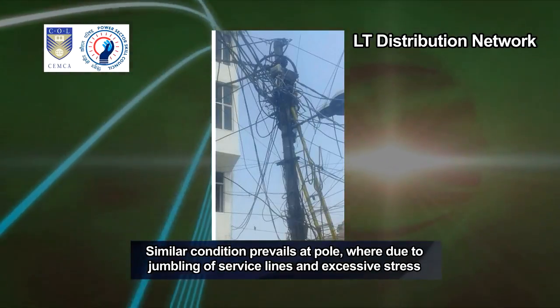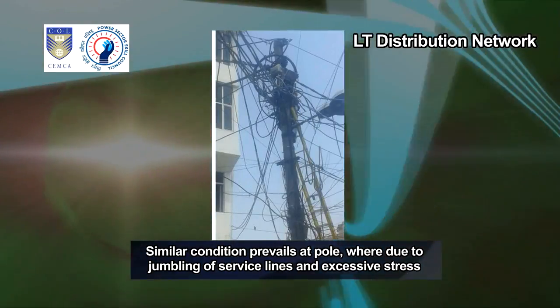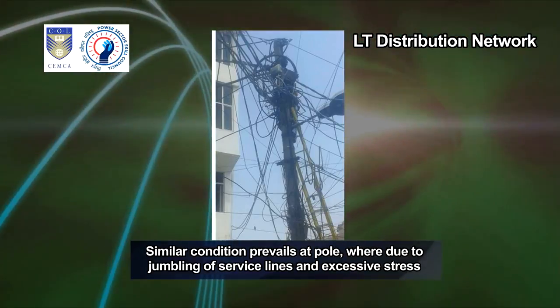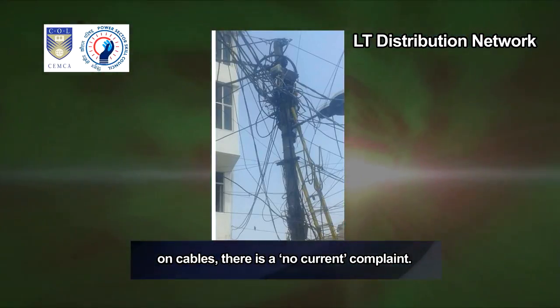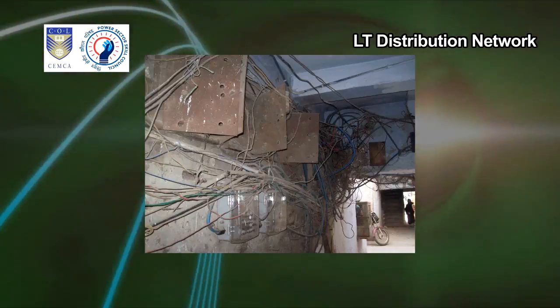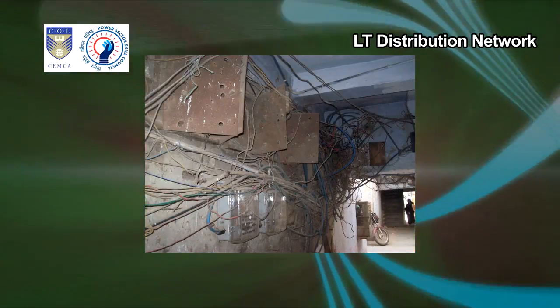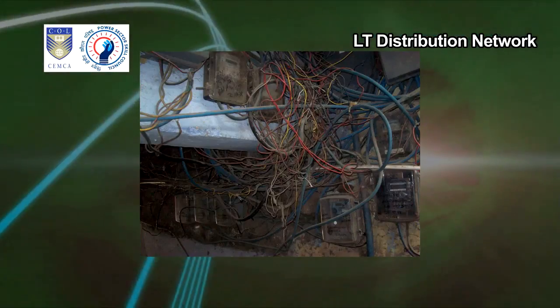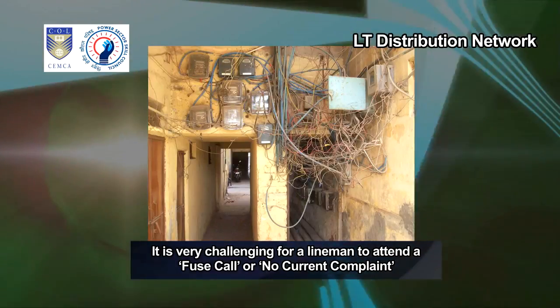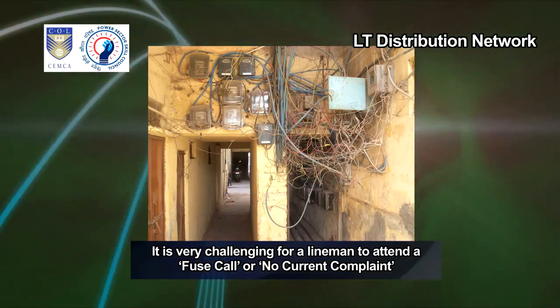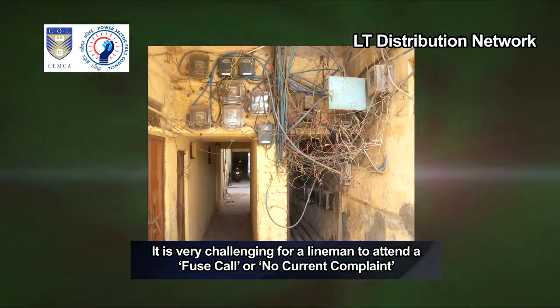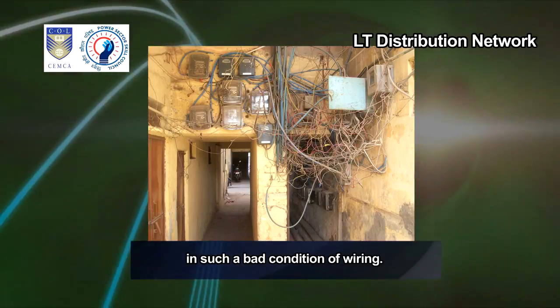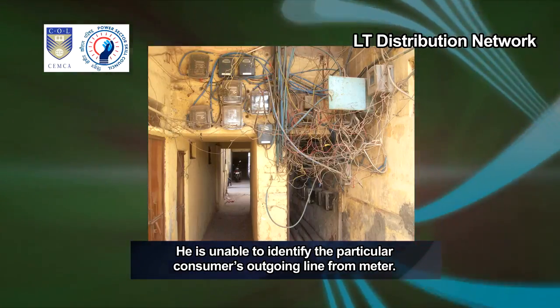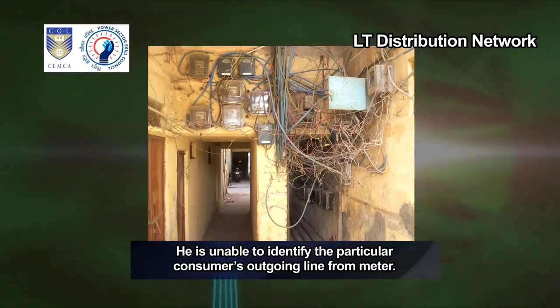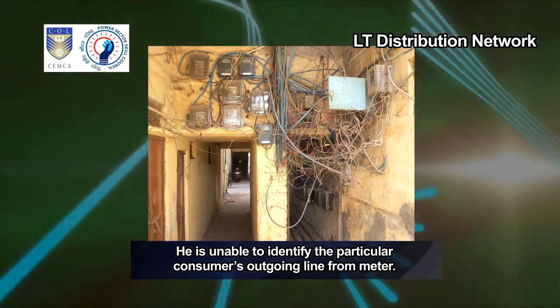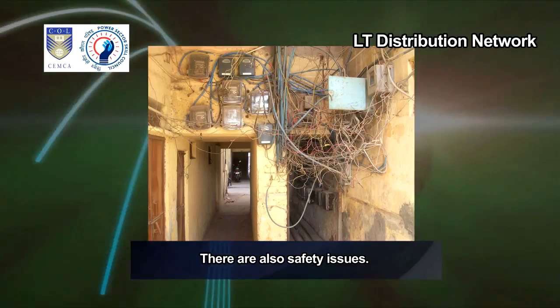Similar condition prevails at pole, where due to jumbling of service lines and excessive stress on cables, there is a no current complaint. It is very challenging for a lineman to attend a fuse call or no current complaint in such a bad condition of wiring. He is unable to identify the particular consumer's outgoing line from meter. There are also safety issues.